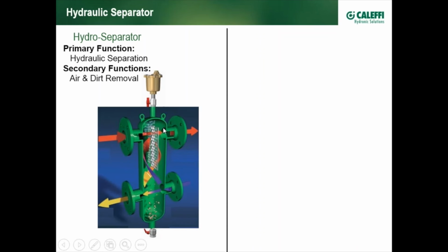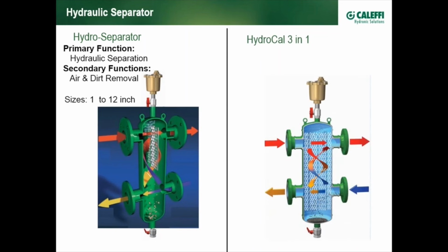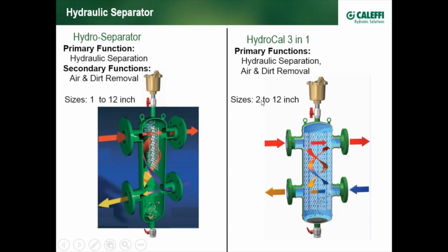hydraulic separator. Now, a question you might ask is, well, can I get rid of my air separator? Well, it depends on the job and perhaps the source of air coming into the system and how quickly you want to get rid of it. However, to ensure the same capacity of air separation and dirt separation you would find in dedicated components, Caleffi designed a sister line called Hydrocal, which has all three functions built in one. We got rid of the baffle plate and replaced it with a specially designed mesh that allows for hydraulic separation, coalescing air separation, and dirt separation, all done highly efficiently. So its primary functions are all three, available from 2 to 12 inch.